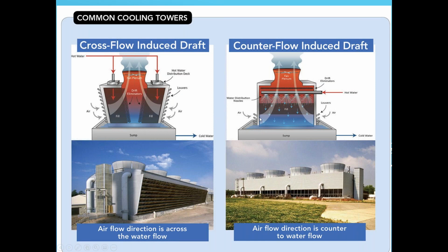The counterflow cooling tower is quite different. As you see, the air inlet louvers are only at the bottom. The walls are square. The return risers are just 5 to 6 feet above the air inlet louvers, and that shows where instead of 30 feet of packing, we would probably have 5 to 6 feet of film fill in the counterflow cooling towers.